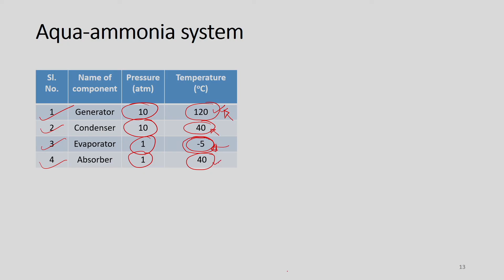Here, these are the solar collectors. Okay. These are connected in series and parallel based on the requirement of the temperature, and this one represents the generator, then 2 is the condenser, 3 is the expansion valve, and then this is the evaporator where space cooling is required, and then we will have this absorber, and then we will have a liquid pump, and it will pump back to the generator, right. So, in the aqua-ammonia system, we will use an ammonia and water solution here. Why ammonia? Because the boiling point of ammonia is about -33 degrees C, and it is very soluble in water. This principle is applied in cooling of a room or cooling of space, right. So, here ammonia is the refrigerant and water is the absorbent, right. So, here ammonia and water are mixed.